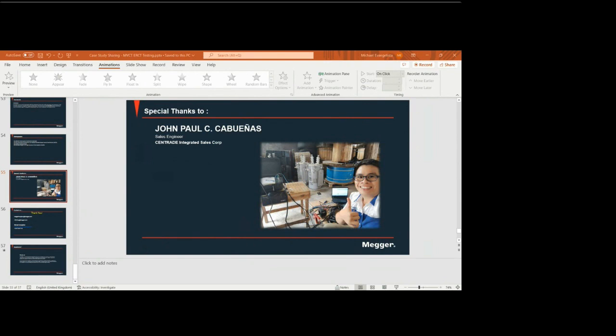Okay, when we are doing CT tests on site and we get an unexpected result, especially when those CTs don't have any nameplate, the good thing with the MBCT is that it will estimate the nameplate of the CT. So you can already assess the CT using those results taken from the MBCT. You can already assess the accuracy, the winding resistance, the saturation curve, and then you can decide whether you put it back in service or not.